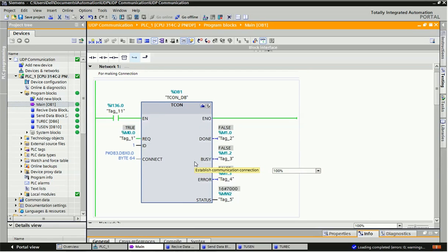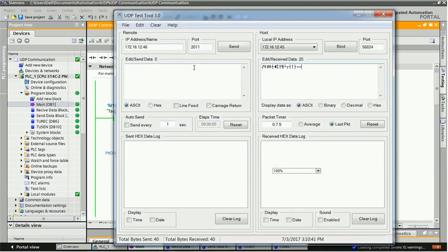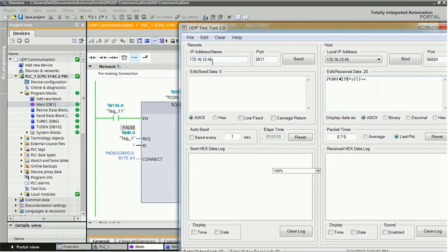First we will send data from the UDP client to the PLC. For sending data from the UDP client we need a UDP tool — there are many open-source UDP tools available on the internet. I have used UDP Test Tool 3.0. For sending the data I assign the PLC IP address 172.16.12.46, and the port number which we configured earlier for making the connection.